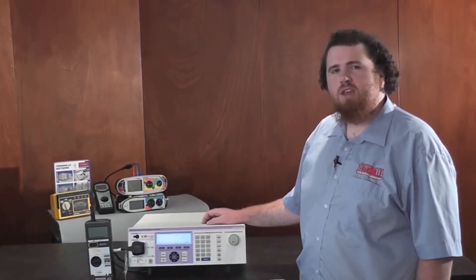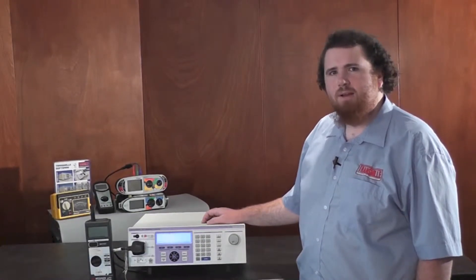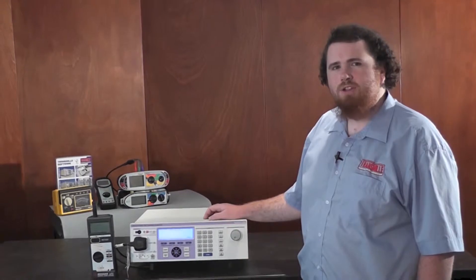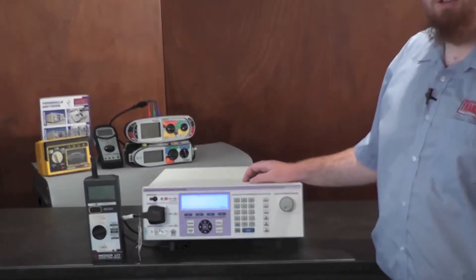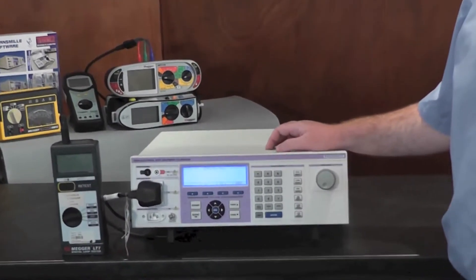Calibrating a loop tester with the 3200A is easy, especially with the auto loop function that automatically adds the loop resistance to the value indicated on the 3200A.